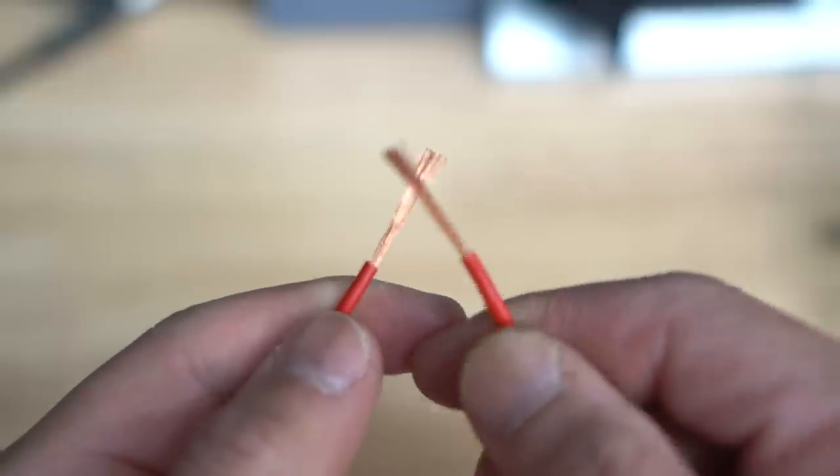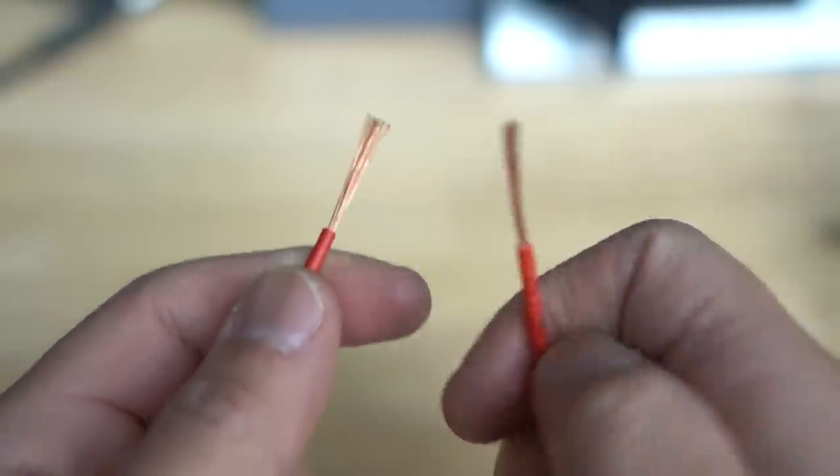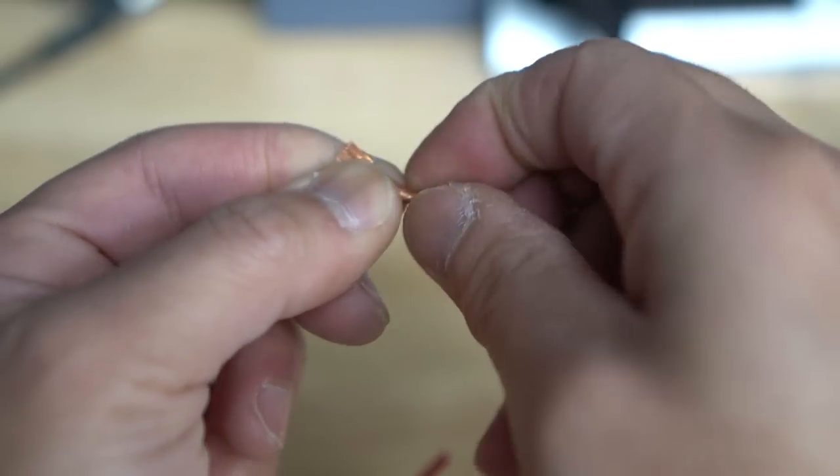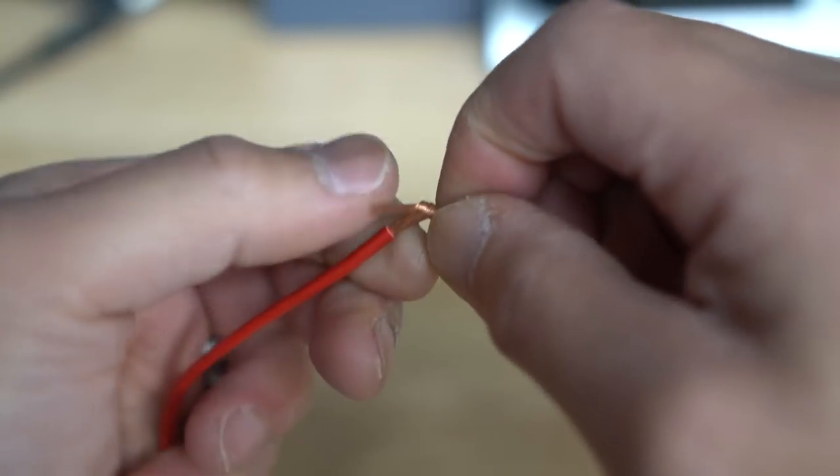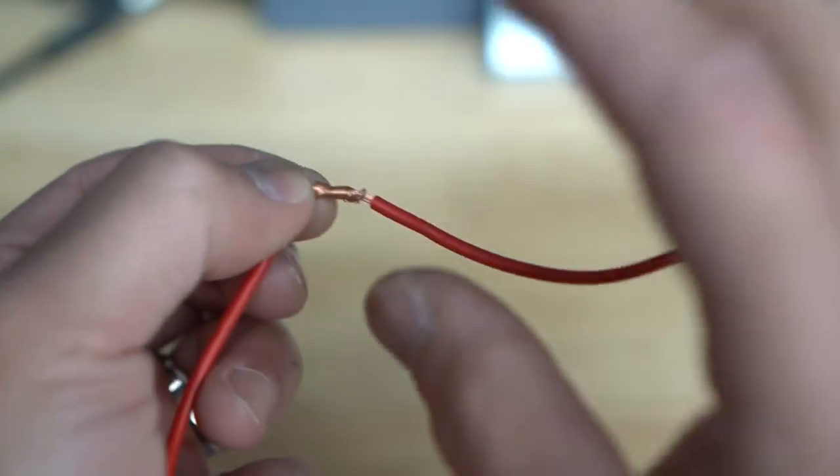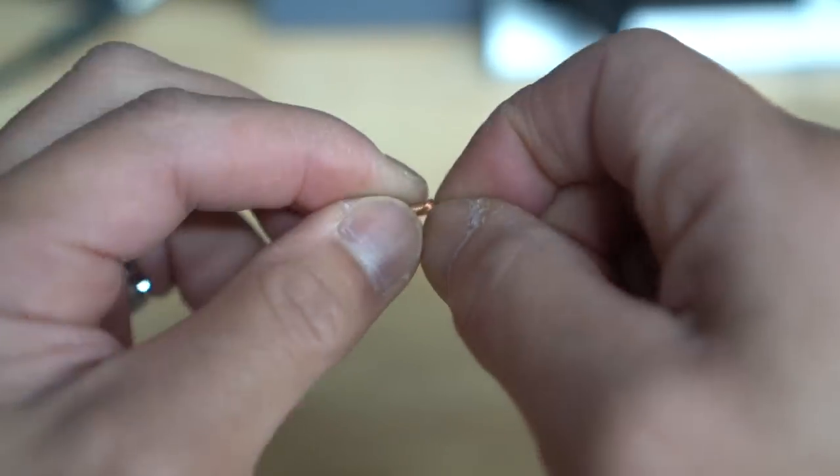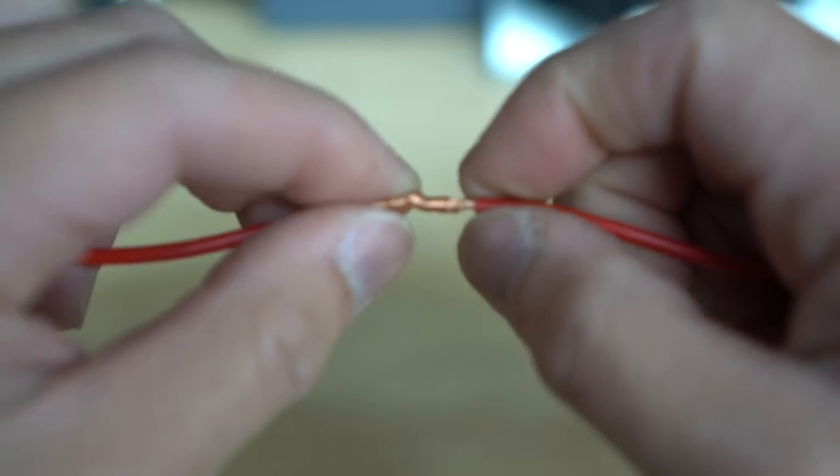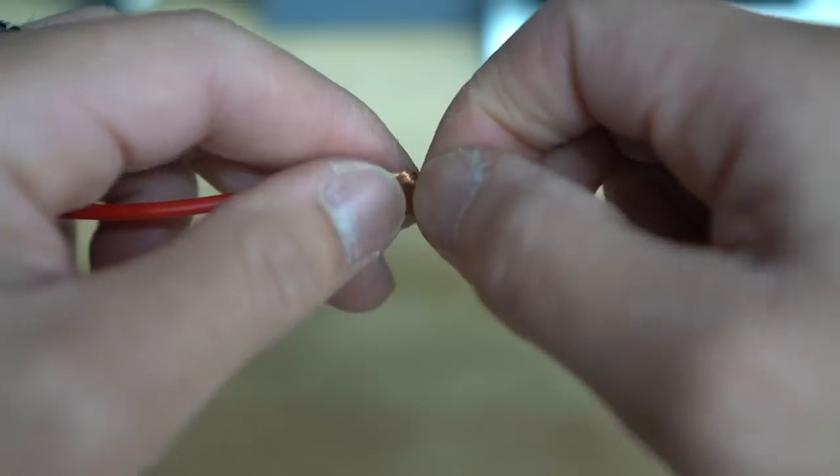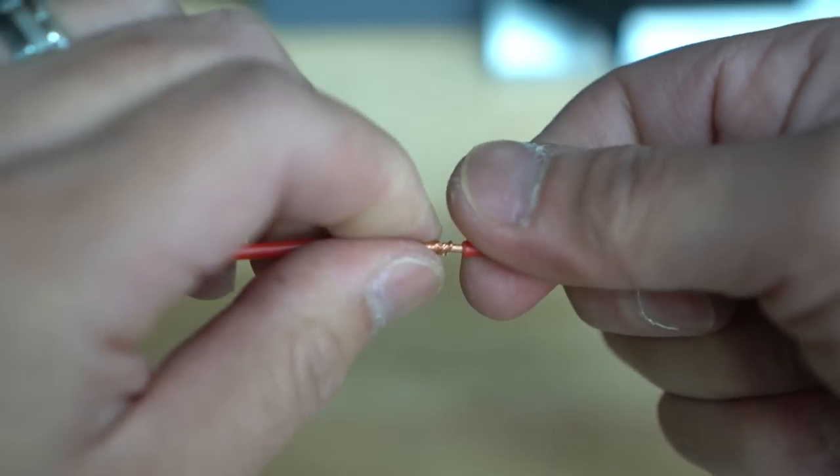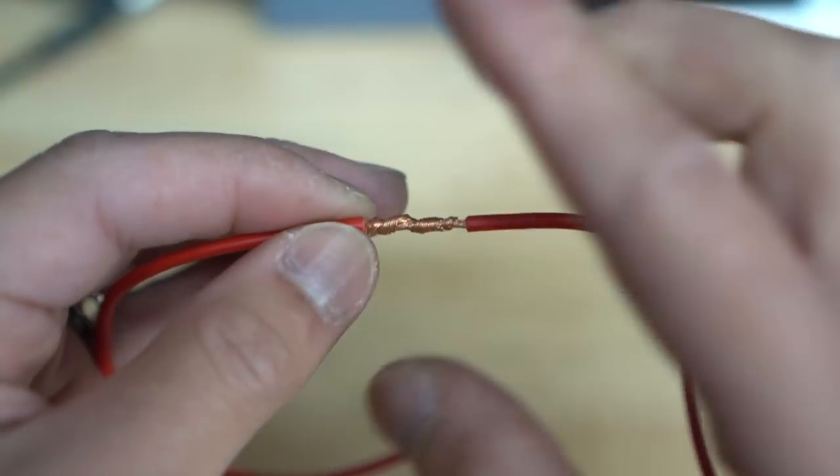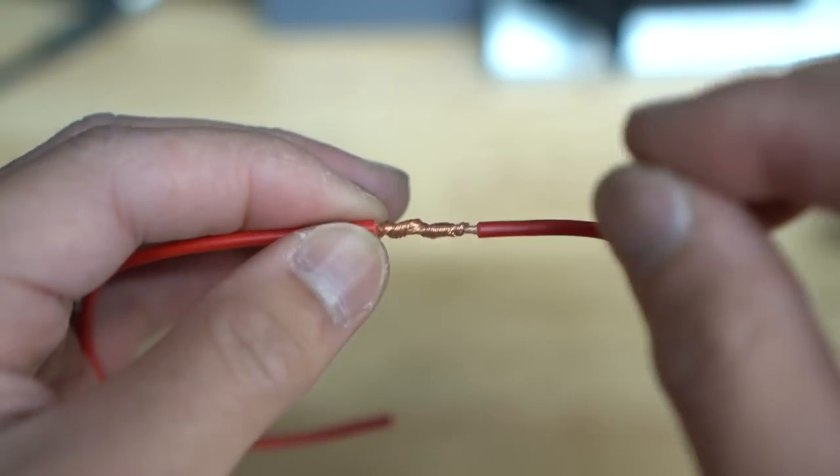The one I do recommend is the lineman splice or the western union splice, which I'll show you right now. Lineman splice or the western union splice is a lot more reliable, and it's very easy. All you have to do is strip your stranded wire, just like so, and you're going to cross it like this. One goes clockwise. The other one goes counterclockwise. And you're just going to feed it right through about three to four circles around. So that's one, two, three. And you're going to do the same thing on the other end. Given this is just an example, but if you are going to do this on a closed wiring system, you are going to put a sleeve first or a shrink wrap sleeve over there.